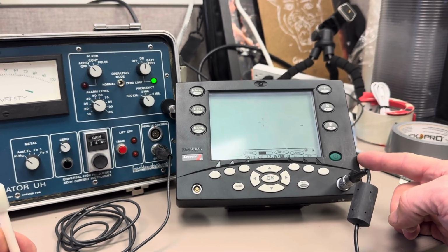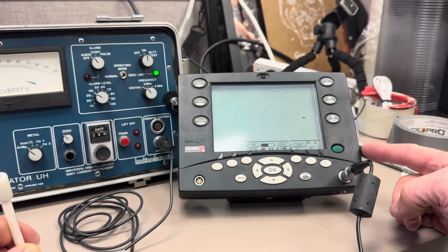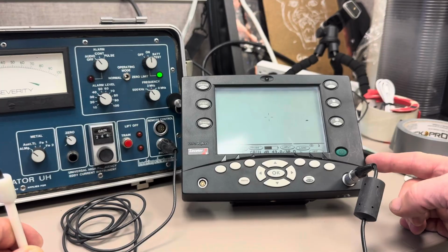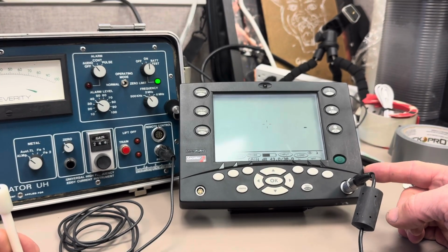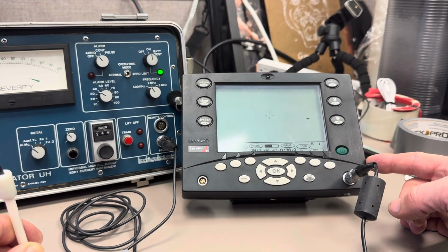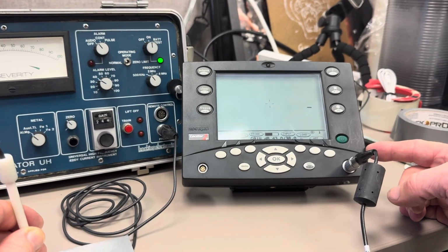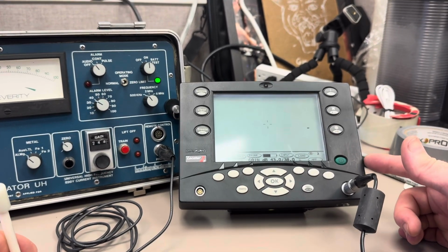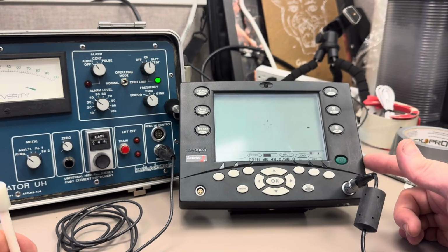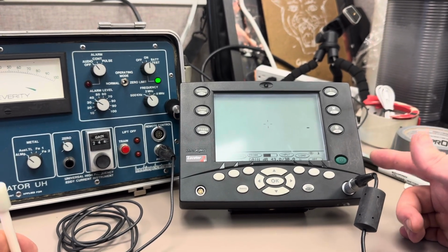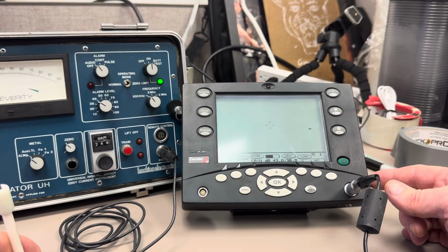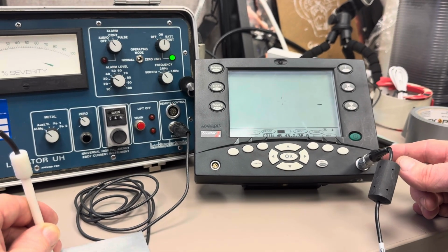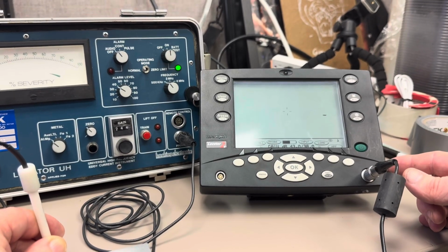If you've got a Lissajous and you've got a gain control and phase control, and you can apply filtering, high pass filters, low pass filters, you're going to have all the basic settings that you're going to need to perform most tests. With this particular tester, I've done liftoff test, conductivity test, weld scanning, and many others. So the point of this video is just to point out that if you have a non-calibrated display, that just means you have more flexibility in your instrument.